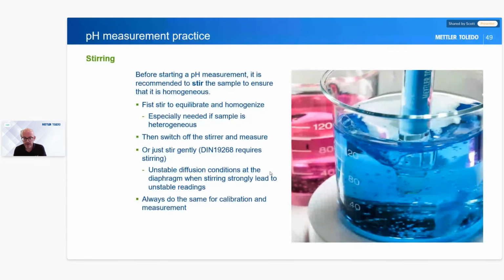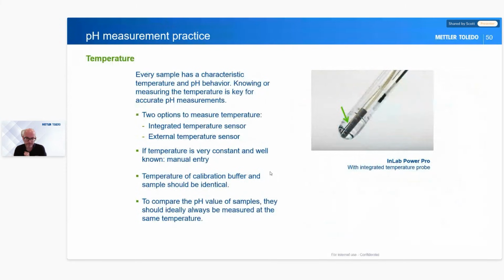Now, when we're taking measurements, we generally don't want to stir, because when we stir we introduce air into our sample, and that air can introduce other things like carbon dioxide, for example. So we need to switch off the stirrer and then take a measurement. Some methods, the DIN method, for example, require stirring. So if we are going to do that, we need to make sure the stirring is at a low speed. It's not mixing or swirling the sample, yet again, to stop that air.